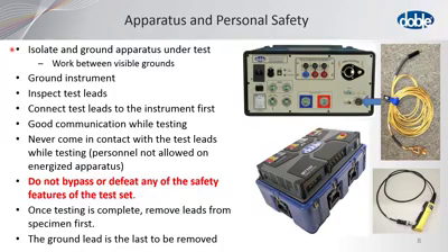Now, you should never come in contact with the test lead while testing. And personnel are not allowed on the apparatus while there is test voltage, right? And do not bypass or defeat any of the safety features. Now, just for example, on the lower right-hand of the screen, we show a safety switch, right? This also can be called an enabling switch, in that this switch must be depressed to the first position for the test to be able to be performed.